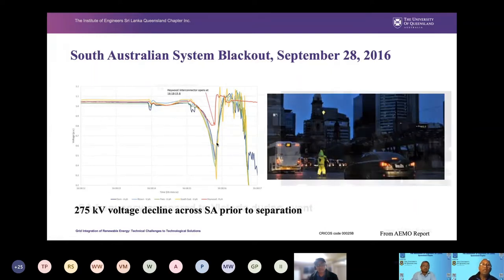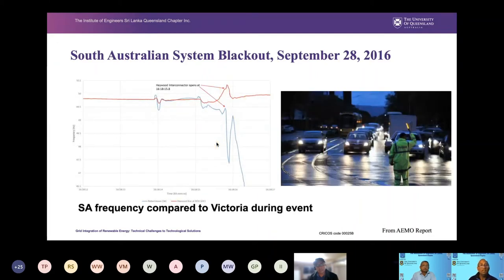And then if you look at the frequency trace, you can see on the other side of the interconnection, that means the Victorian side, the red line, and the yellow one, the blue one, is on the South Australian side. So as a result of high generation on the Victorian side, the frequency shot up. As a result of low generation and more demand, the frequency dropped, and then it dropped to a point that it couldn't recover. It collapsed.